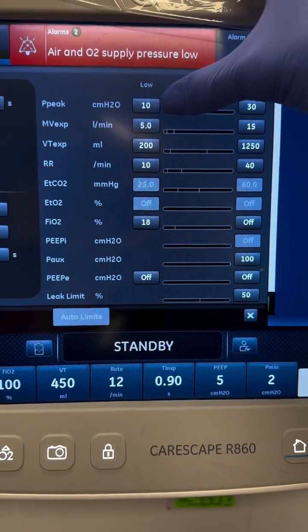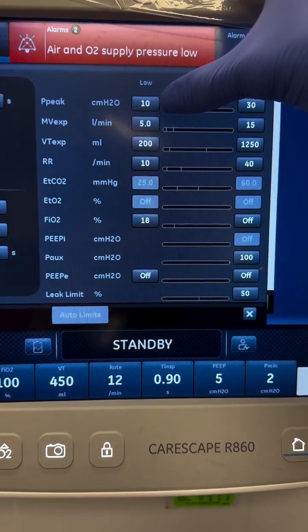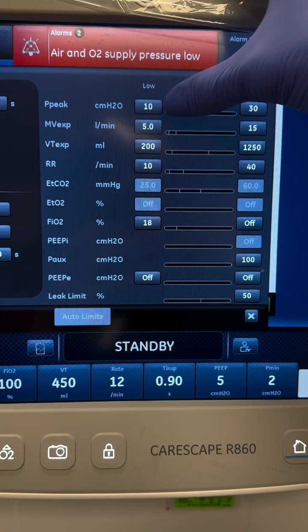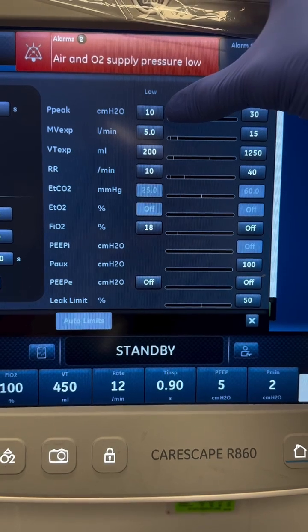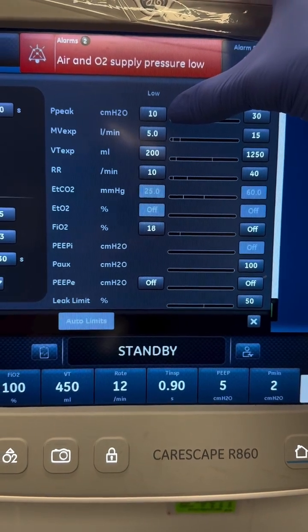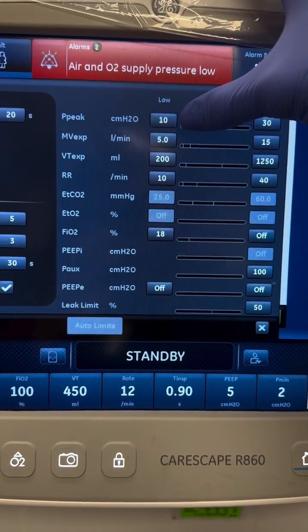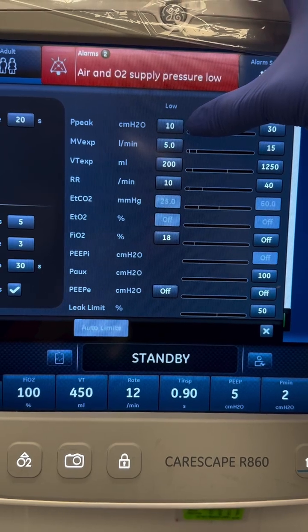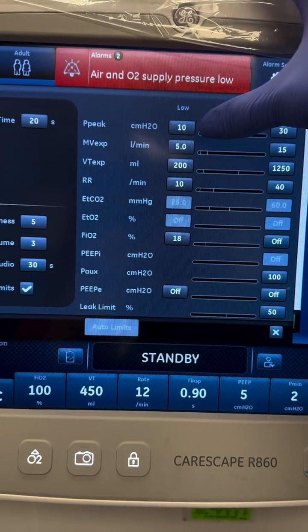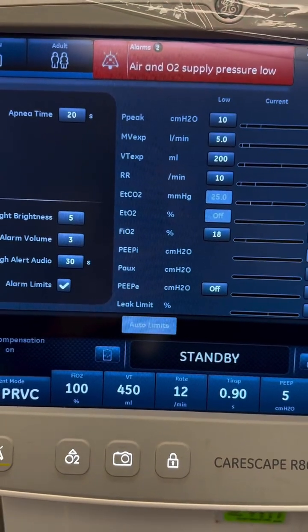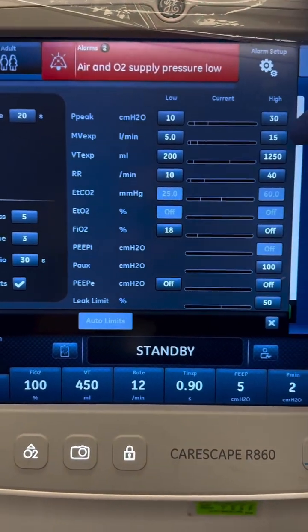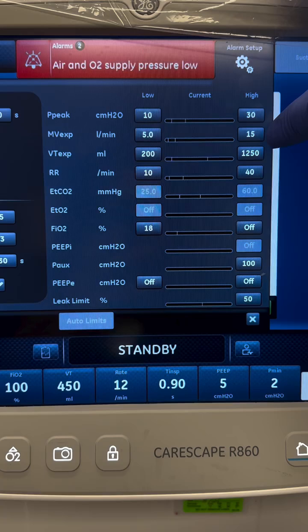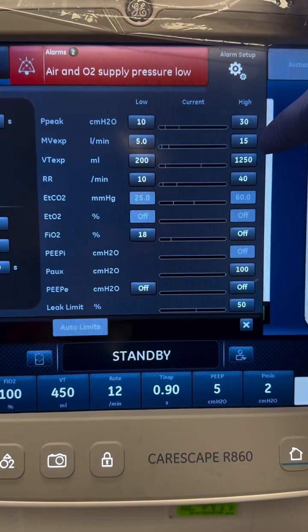Next, low peak pressure indicates that air is leaking out. Think something is disconnected, there's a leak, or examine your ET tube or trach. To fix it, you're going to reconnect something, check your cuff, and review that circuit.